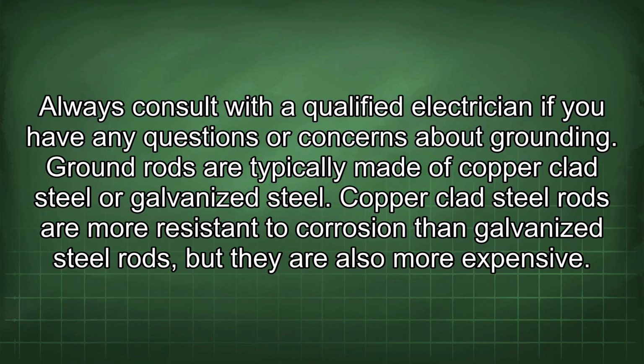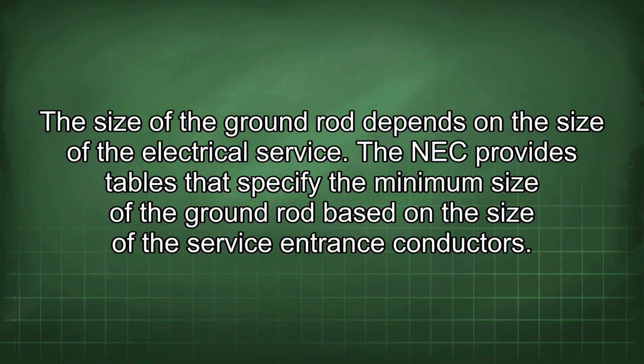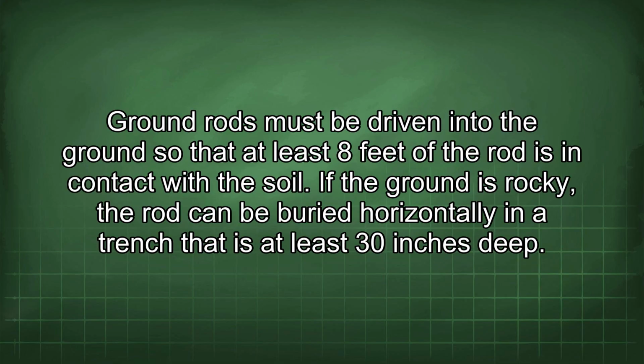Ground rods are typically made of copper-clad steel or galvanized steel. Copper-clad steel rods are more resistant to corrosion than galvanized steel rods, but they are also more expensive. The size of the ground rod depends on the size of the electrical service. The NEC provides tables that specify the minimum size of the ground rod based on the size of the service entrance conductors. Ground rods must be driven into the ground so that at least 8 feet of the rod is in contact with the soil.